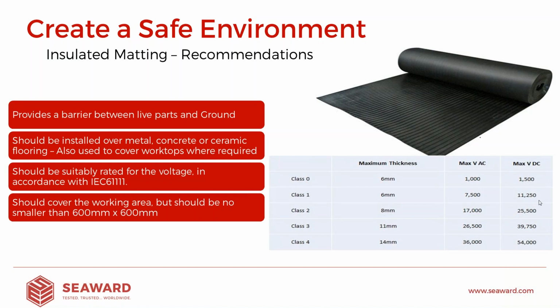That would be the minimum that we would recommend for anyone using any of the Clare testers or the Seaward testers. You will know that they have generally a maximum voltage output of 5,000 volts AC and 6,000 volts DC. So we want to make sure we're at least capable of withstanding the maximum output of the test equipment. In terms of the sizing of the rubber matting that you do choose to use, there's no maximum size, but it should be sufficient to cover the working area. Certainly if the operator has to move around, consider all of the points at which he may need to stand and ensure that rubber matting is covering that area.